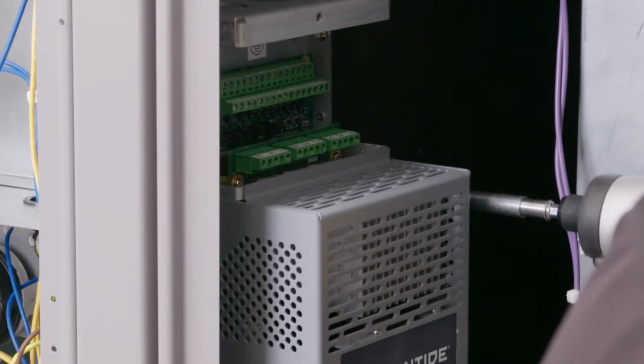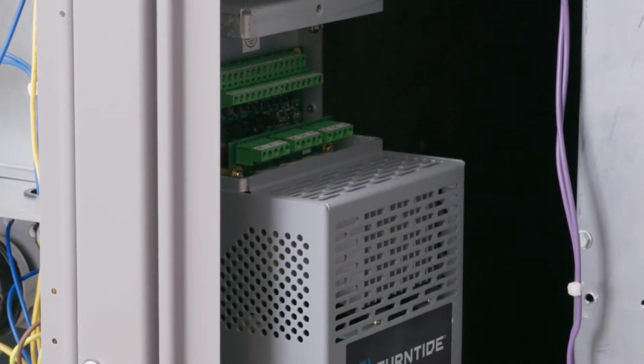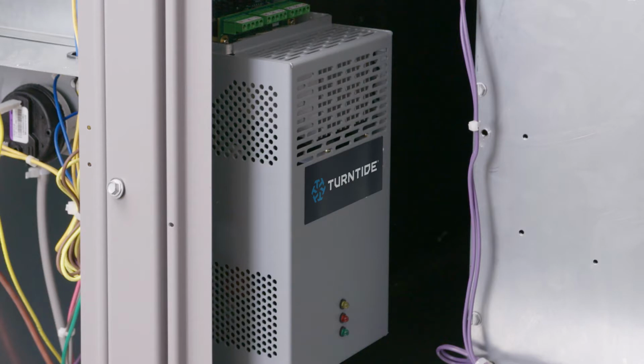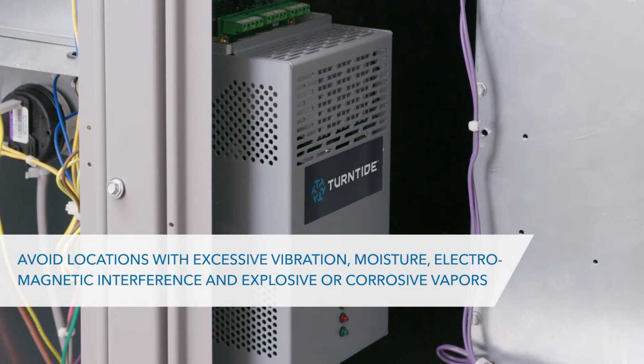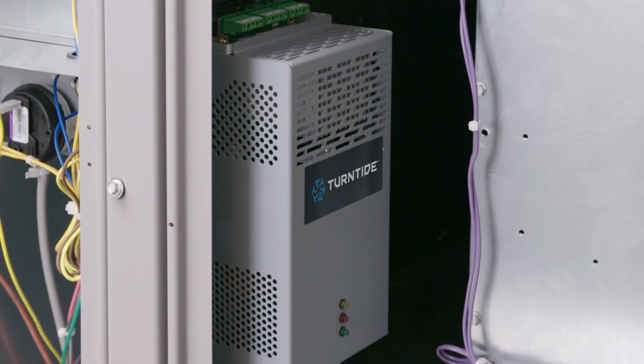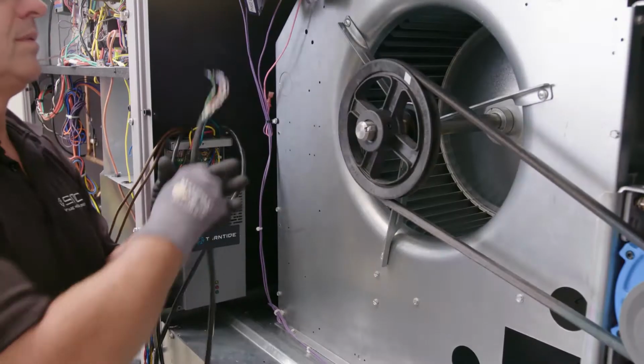The motor controller can be mounted to any rigid surface with a minimum clear space of 3 inches on all sides. Note the controller itself can be mounted in any position without impacting functionality. Make sure it's located away from excessive vibration, moisture, electromagnetic interference, and explosive or corrosive vapors. There's no limit to the distance the motor controller can be mounted away from the smart motor, but the closer it is to the smart motor, the easier your installation will be.